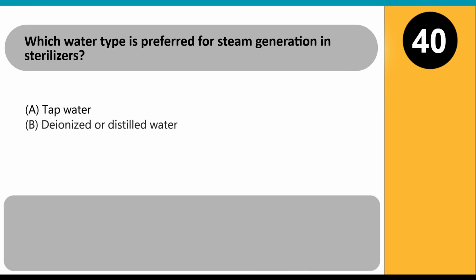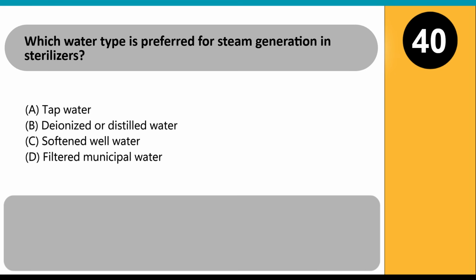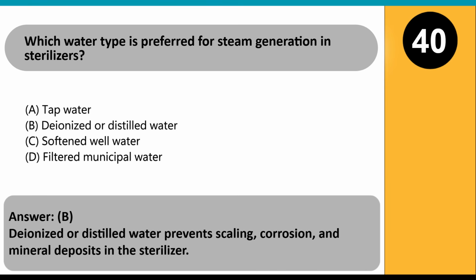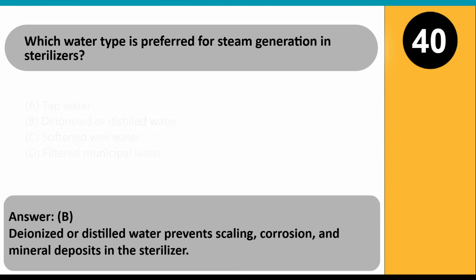Which water type is preferred for steam generation in sterilizers? A. Tap water. B. Deionized or distilled water. C. Softened well water. D. Filtered municipal water. Answer B. Deionized or distilled water prevents scaling, corrosion, and mineral deposits in the sterilizer.